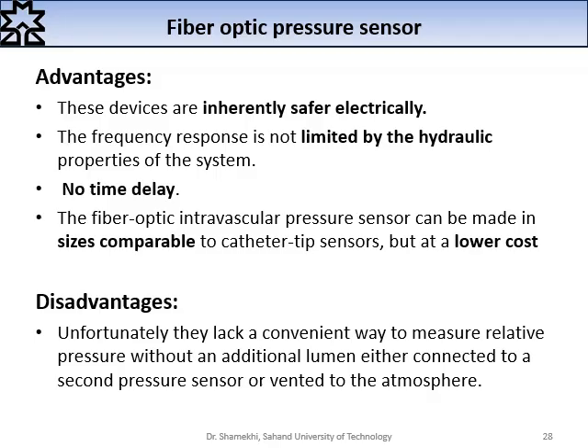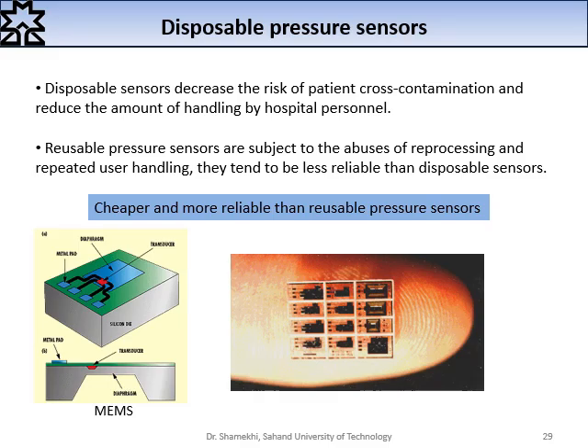But we have an important disadvantage. As I mentioned before, unfortunately, they lack a convenient way to measure relative pressure without an additional lumen, either connected to a second pressure sensor or vented to the atmosphere. Therefore, we need a second pressure sensor, and also we need a servo motor system to control the pressure inside the sensor. We have a complex system at the outside, at the main part of the sensing device. Disposable pressure sensors, as you can see in these figures, decrease the risk of patient cross-contamination and reduce the amount of handling by hospital personnel. Reusable pressure sensors are subject to the abuse of reprocessing and repeated user handling. They tend to be less reliable than disposable sensors.